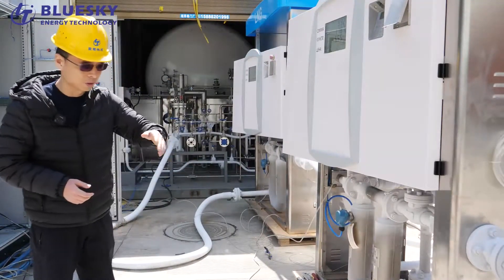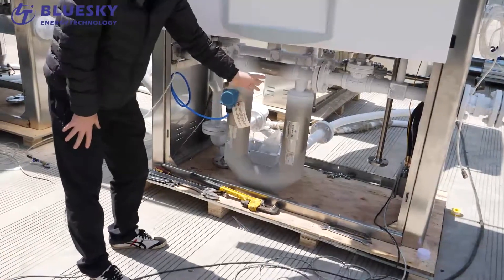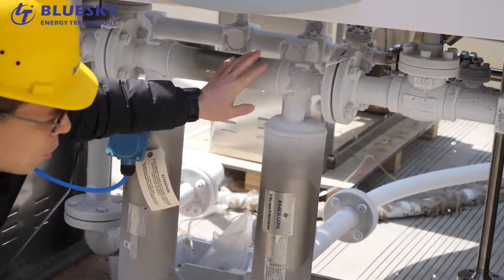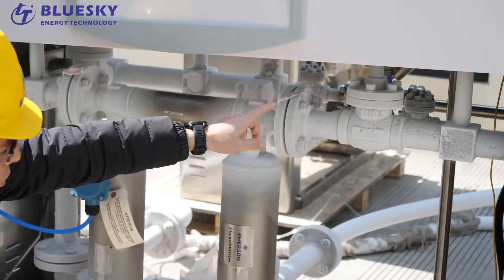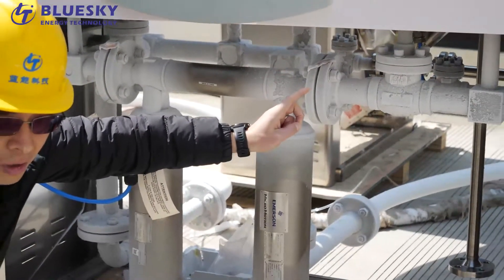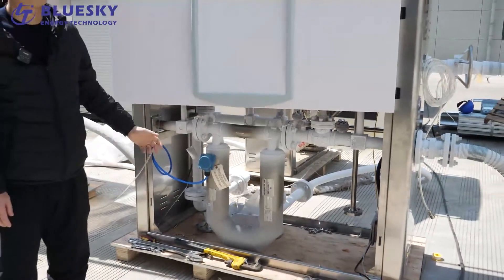You can see the whole structure is like a standard LNG dispenser. This two-inch flow meter is used for liquid coming in for measurement testing. You can also see a smaller mass flow meter for gas return — because if the temperature changes slightly, some liquid will become gas. This gas returns through the gas return pipeline through the small flow meter and back to the tank. When we calculate the total, we reduce this returned gas amount. This is the major principle of a standard LNG dispenser.